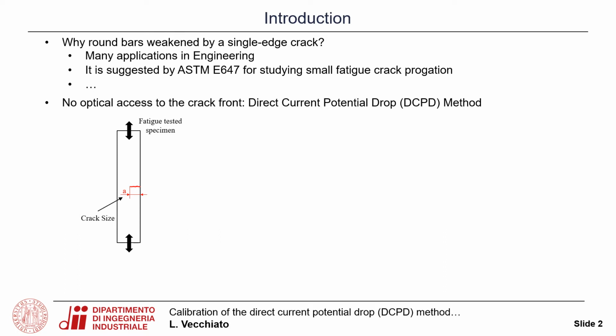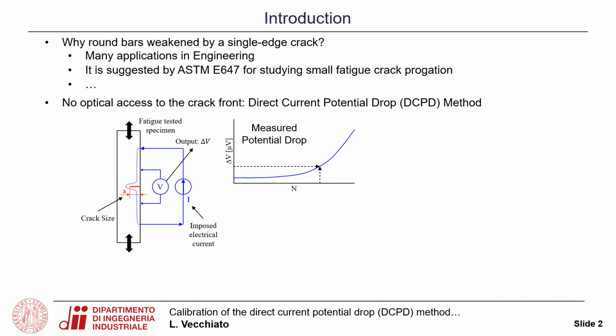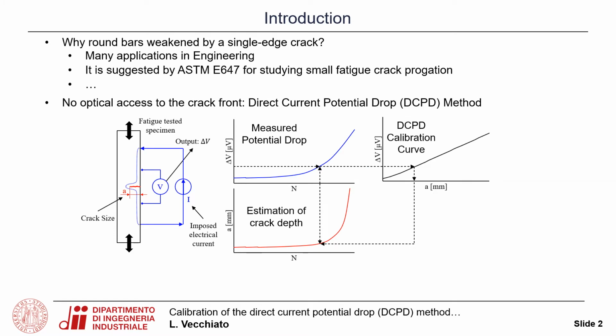The most important drawback of this geometry is that there is no optical access to the crack front. And so for studying crack growth, it is necessary to adopt a non-visual experimental technique, among all the direct current potential drop method. This method consists in imposing the flowing of a constant electrical current through the specimen and measuring the potential drop between 2 points on the specimen itself. By entering a proper calibration curve with the potential drop, it is possible to evaluate the crack size during the propagation.